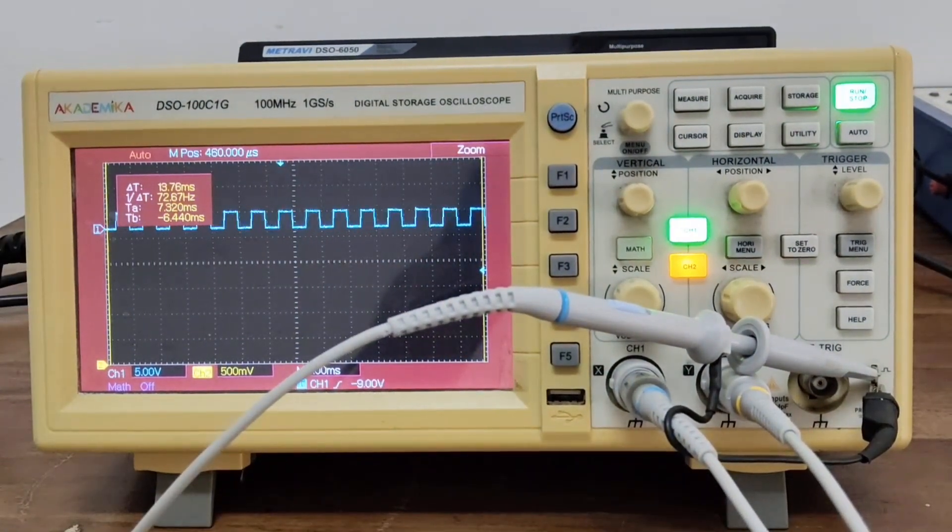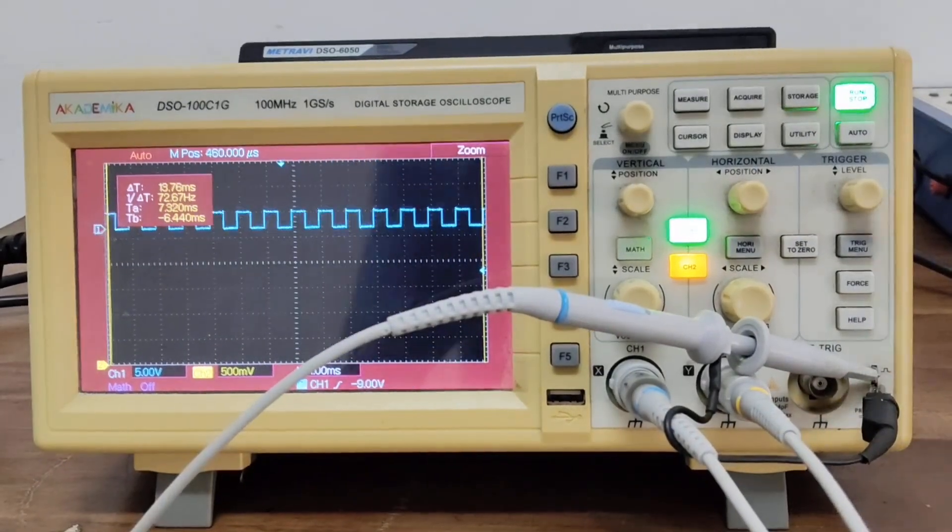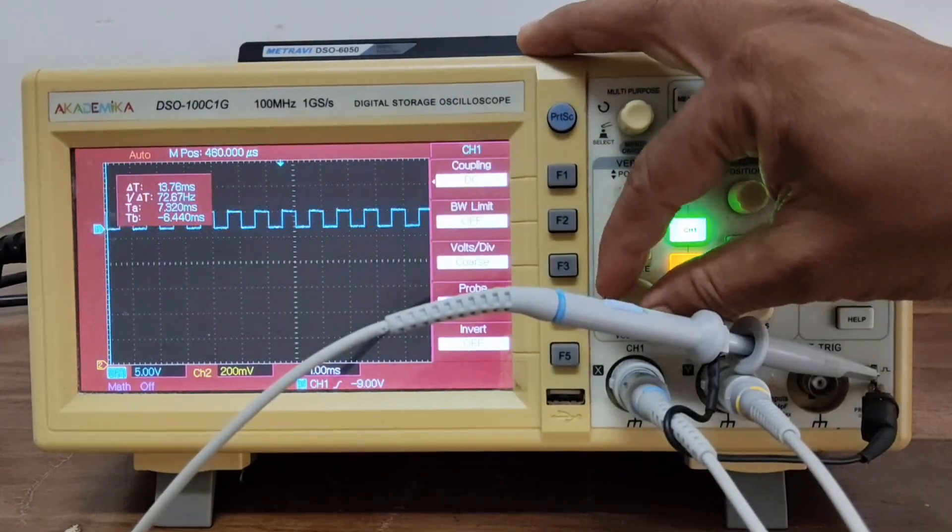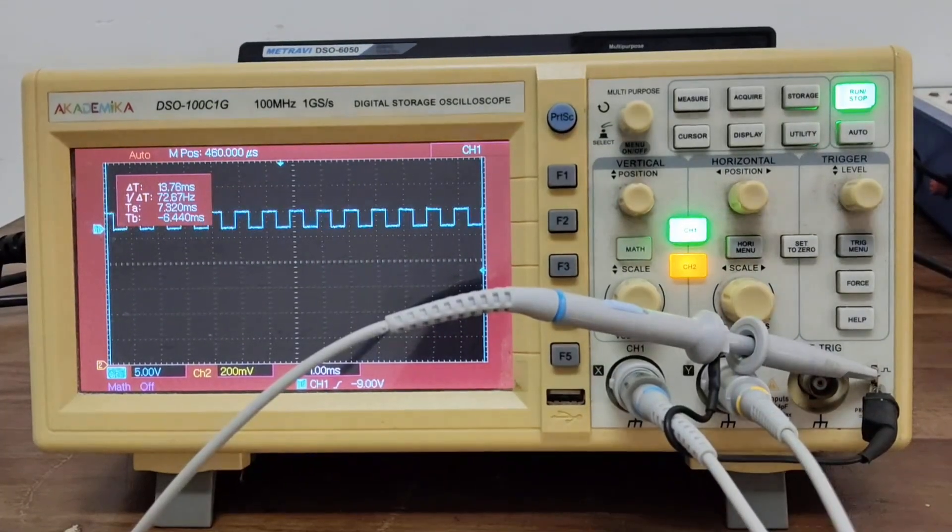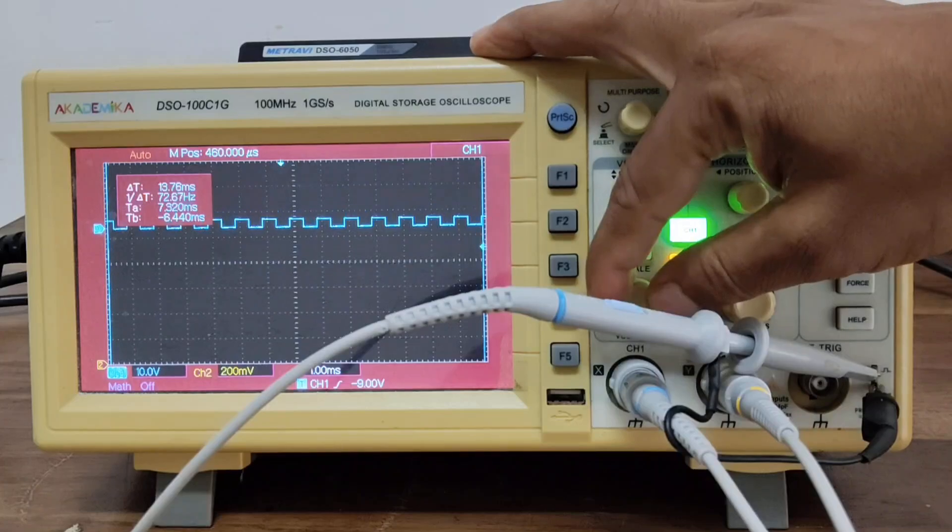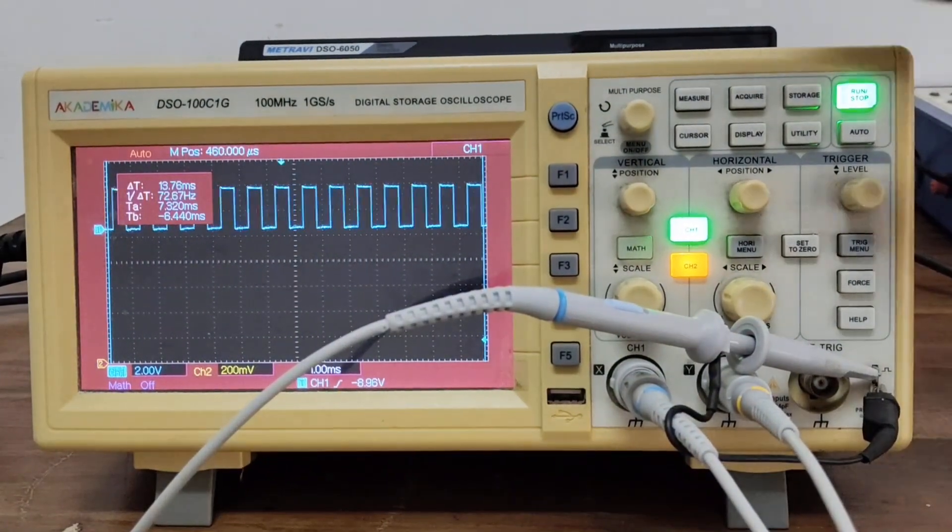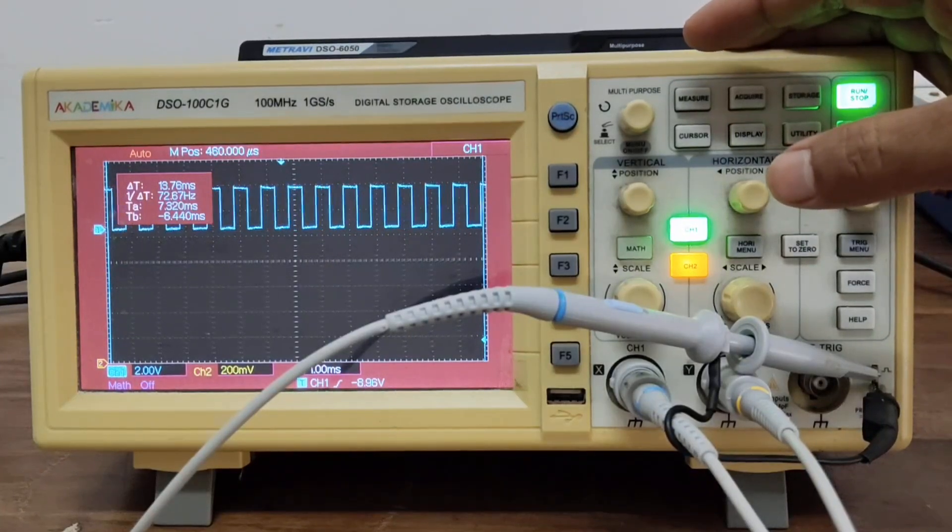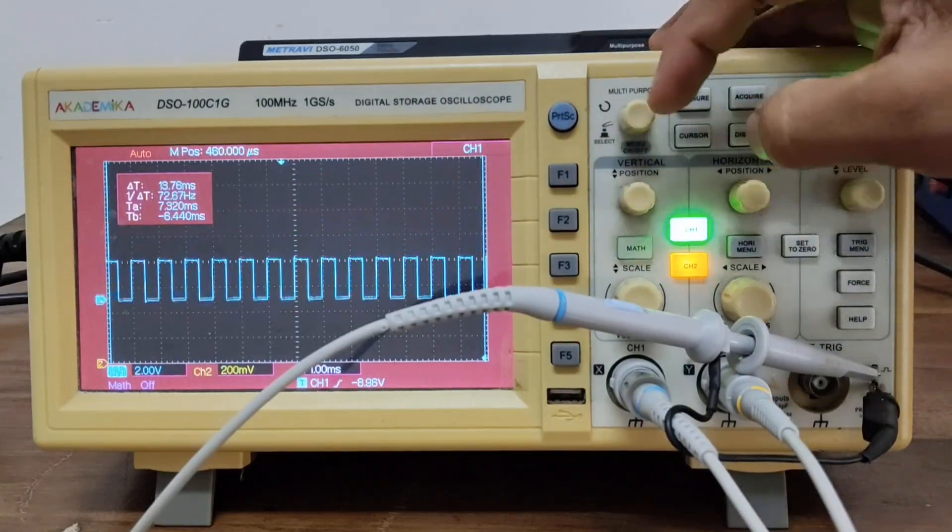Now, what is the next step? Use the vertical knobs here to adjust the vertical scale. You can see, here I have to select the channel first. So I am pressing channel 1, then channel 1 is selected. Now if you change the vertical knob, you can see what happens here. Use the vertical knob to adjust the vertical scale, that is how many volts per division you want to adjust. Make sure your waveform fits well vertically. And this knob will help you move the signal vertically for your clear view.